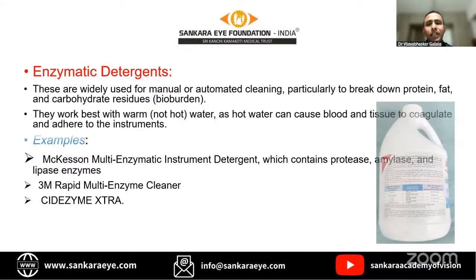These detergents are very effective in cleaning and break down bioburden of all types, like proteins, carbohydrates, fat residues. And it works best with warm water. You should not use hot water because hot water can cause coagulation of blood products. But it is always debatable whether it is really necessary to use enzymatic detergent in ophthalmic instrument cleaning, because we create very little bioburden during our surgeries. And these enzymatic detergents can cause a lot of TASS, like the post-operative inflammation chances are very high. So if it is not really needed, and if you have a protocol, you can use it once weekly, and it is better to go with neutral pH detergents instead of enzymatic detergents.